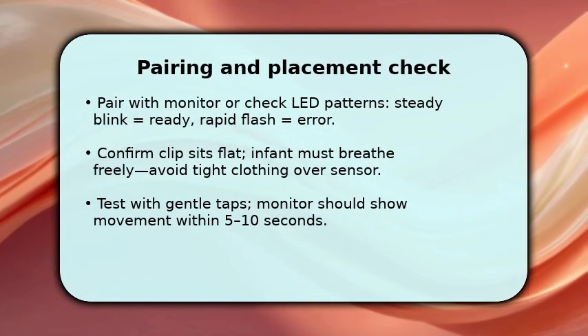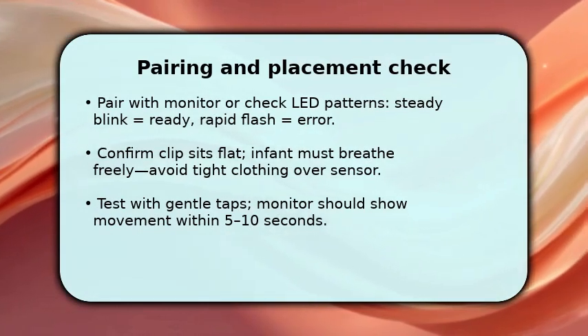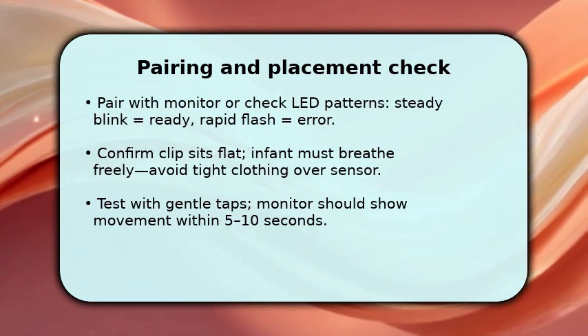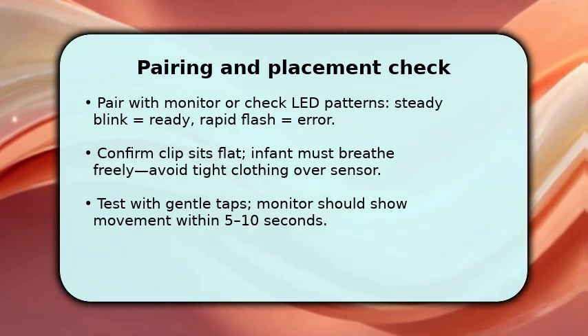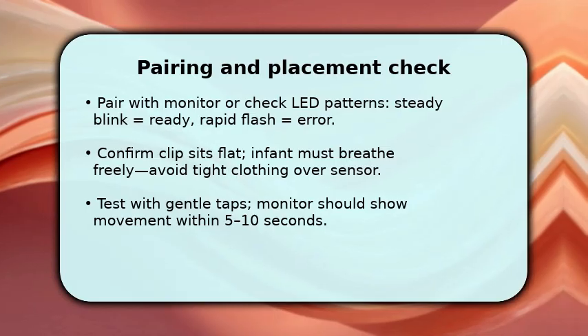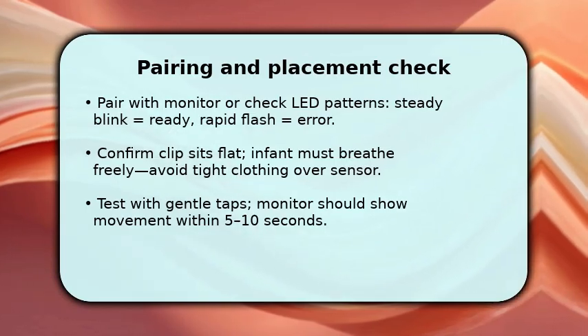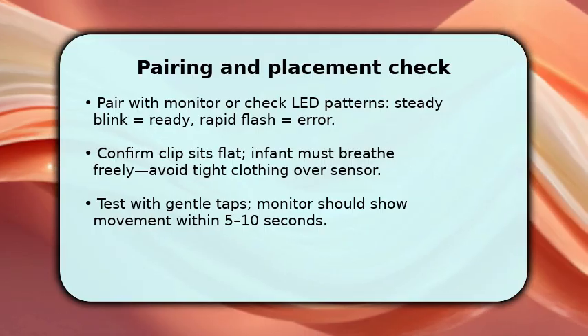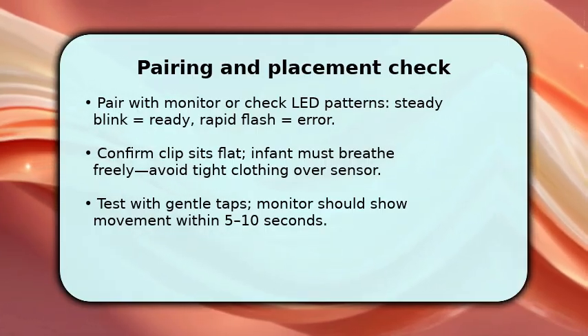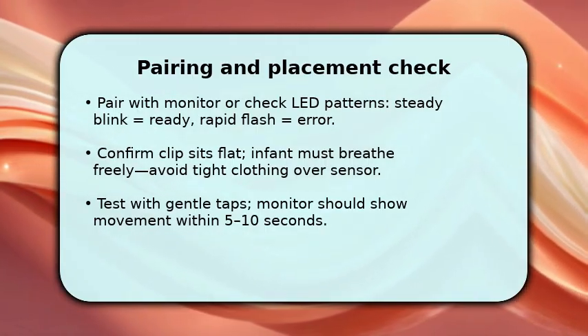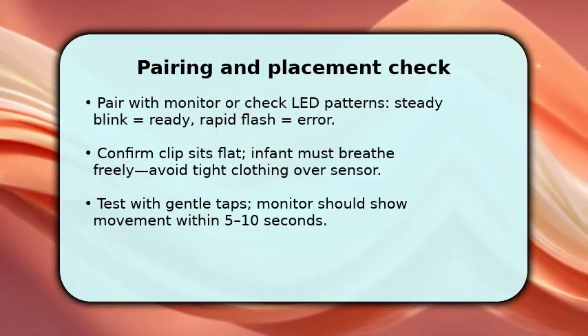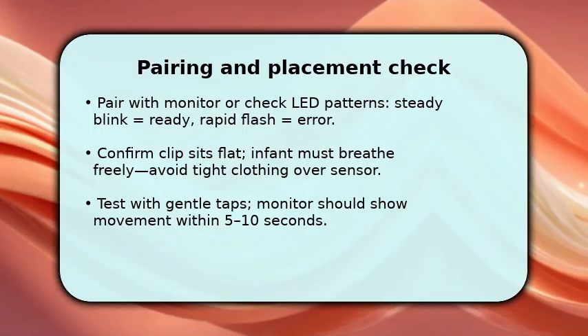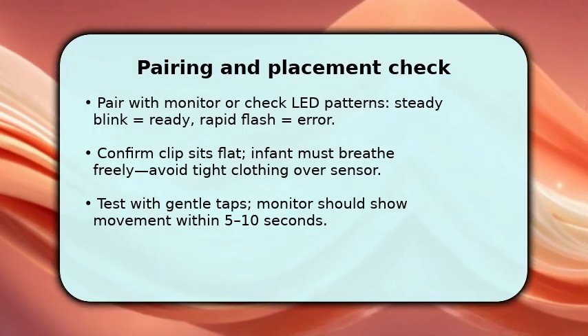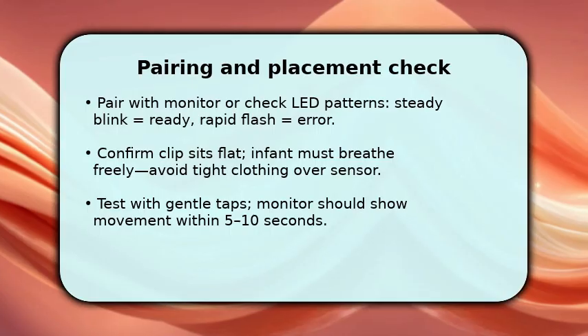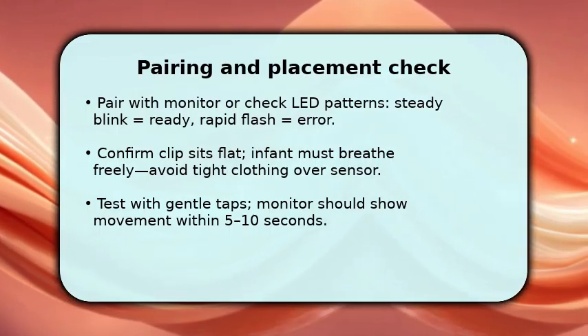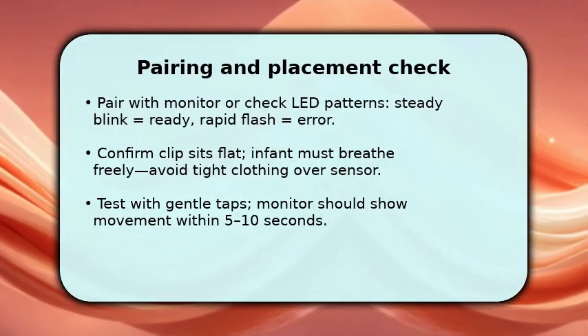You now pair and verify placement so the sensor reads reliably. Begin pairing with your monitor or check the LED. A steady blink means ready, rapid flash signals an error you must reset. Make sure the clip sits flat against fabric and not twisted. This lets the probe detect up and down abdominal motion. Also ensure clothing isn't tight over the sensor so breathing isn't restricted. To confirm, gently tap the abdomen and watch for movement feedback within 5 to 10 seconds.